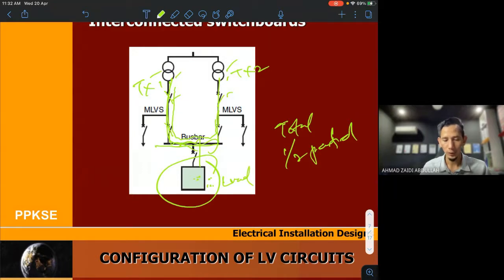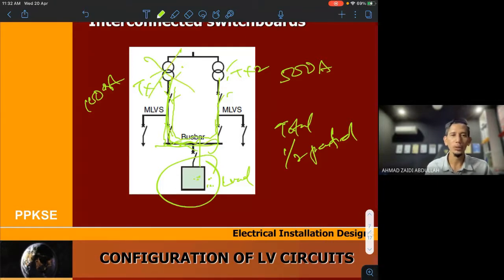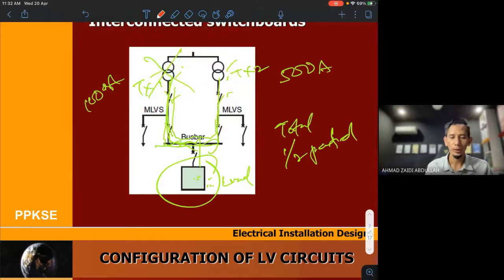You can get only half because maybe in your design you have a lot of load here, and maybe this transformer is 1000 amp but this one is 500 amp. So in normal condition you take supply from this transformer. Suddenly this transformer is shut down. Okay, suddenly this transformer trips. So you open this breaker. So this load can be safe.